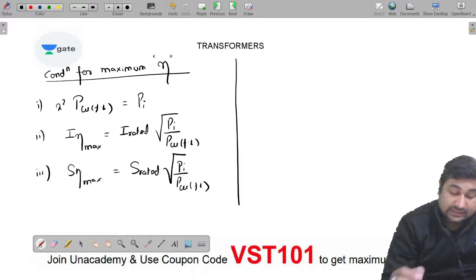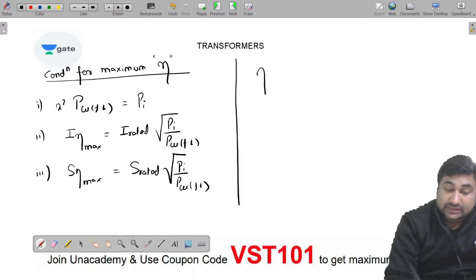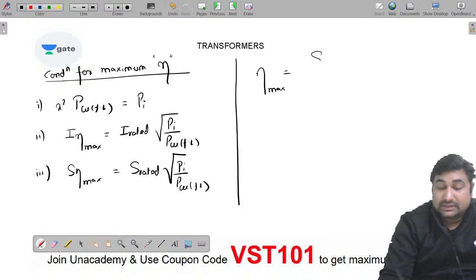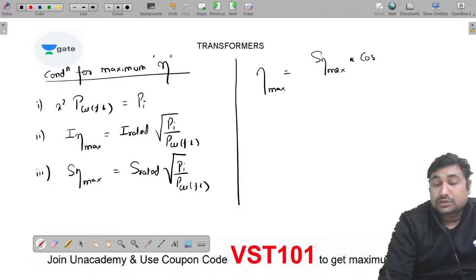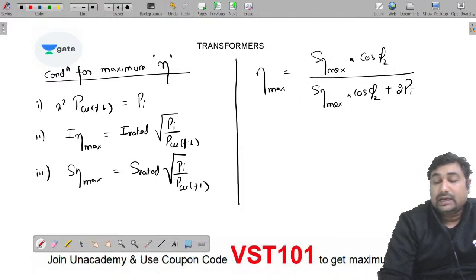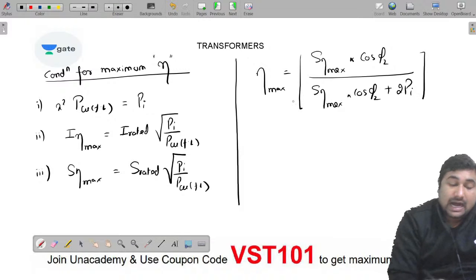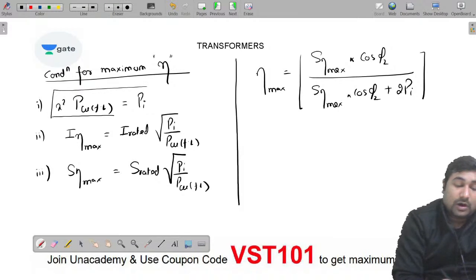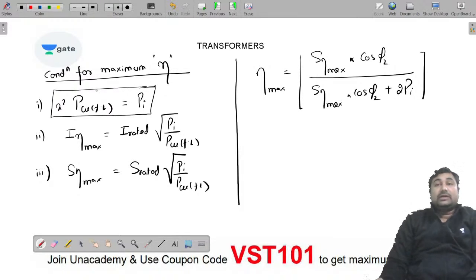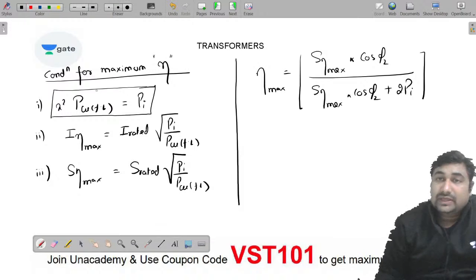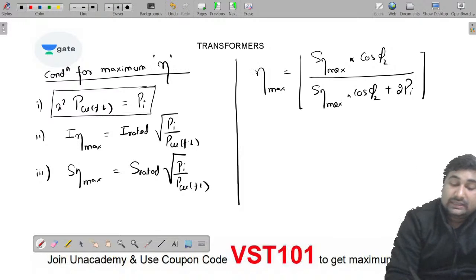KVA at which efficiency is maximum - we are interested in maximum efficiency. Maximum efficiency equals KVA at which efficiency is maximum into cos phi 2, upon KVA at which efficiency is maximum into cos phi 2 plus 2 Pi. Always remember, iron loss equals operating copper loss equals iron loss, in order to have maximum efficiency.